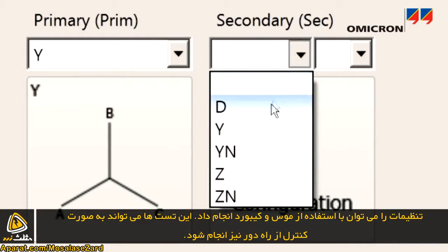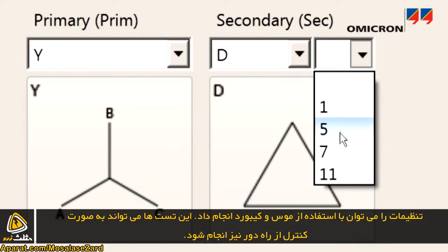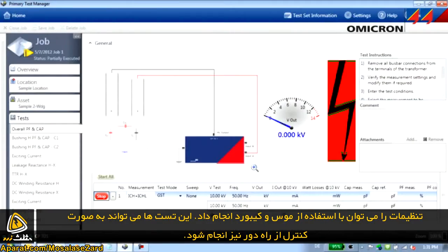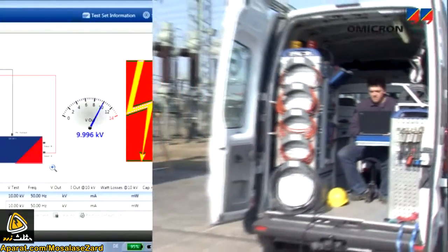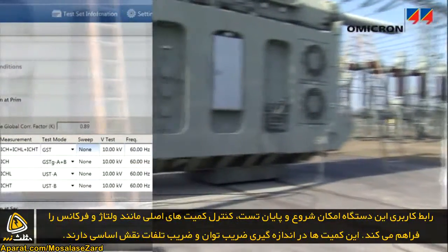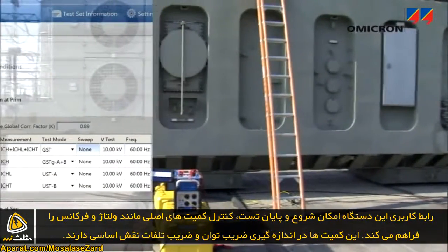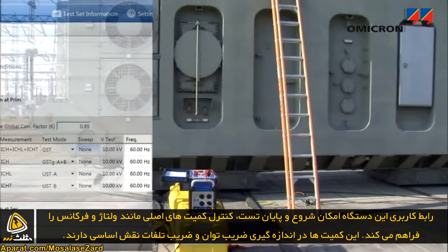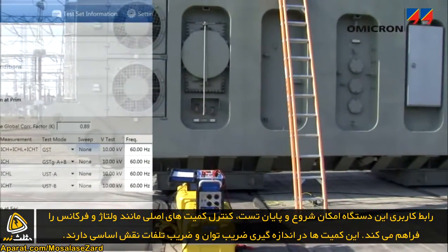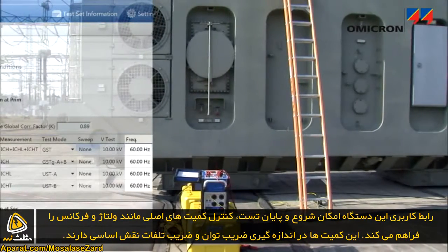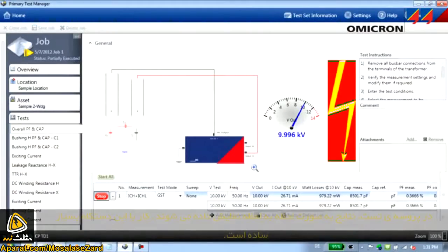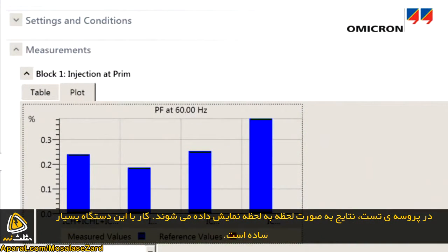Settings can be entered conveniently with a keyboard and mouse. The test can be run and supervised by remote control. The user interface allows the test to be controlled by entering the voltage and frequency values where the capacitance and dissipation factor or power factor will be measured, starting and stopping the test, and supervising the measurement progress and intermediate results.